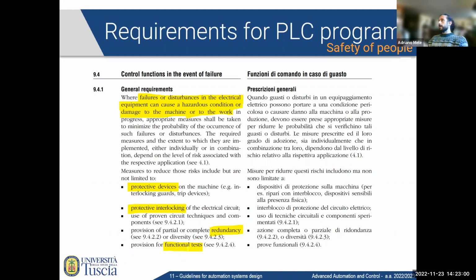Because sometimes, protective devices, so devices that are supposed to enter into operation when a failure occurs, are there, but they will never operate because the machine never breaks. So ideally, those devices could break just because of time passing, and you could never notice because they never enter operation. So there should be a way of testing these devices, even if they are not actually working. This is something similar to what you have in your house. If you take the differential switch in the electrical panel, you have a safety switch which can be used to disconnect the power if you have a short circuit somewhere. And in that case, you have a small button that you can press to test that it's working correctly. That's a very simple example, but you got the idea.